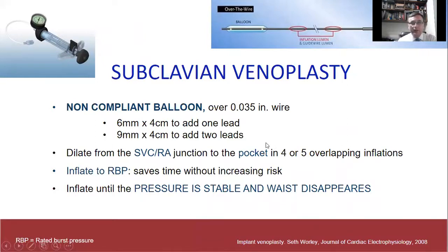For subclavian venoplasty, we use, as I told you, non-compliant, over-the-wire balloons with an 035 wire. The most commonly used balloon is the 6 millimeter diameter and 4 centimeters length for adding one lead. If you need to add 2 leads, a balloon of 9 millimeters diameter is the best. Always dilate from the superior vena cava right atrium junction to the pocket in 4 or 5 overlapping inflations. And always inflate to the rated burst pressure. That saves time without increasing risk. And inflate until the pressure is stable and the waist disappears.